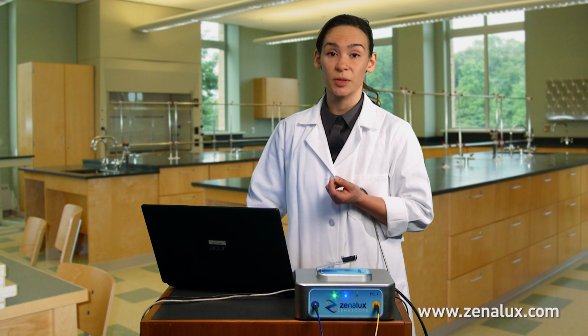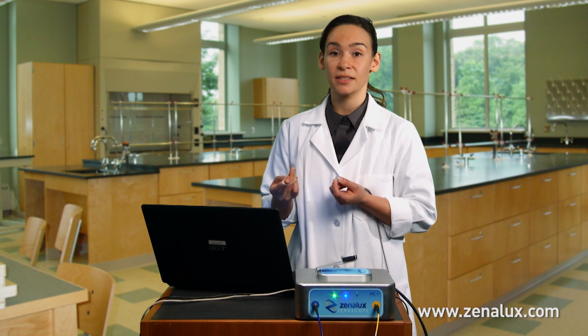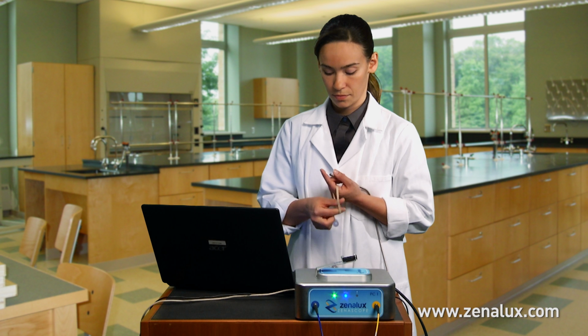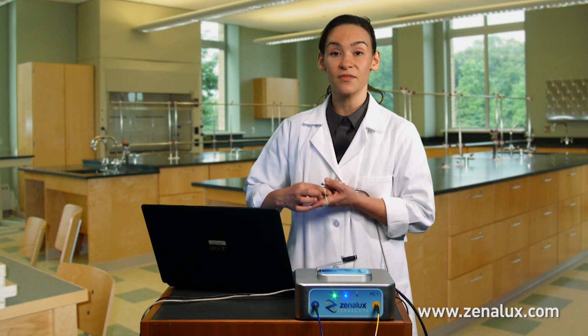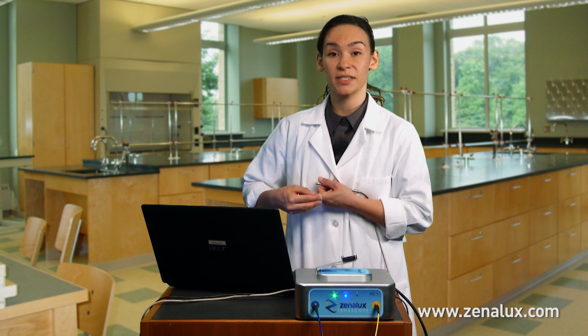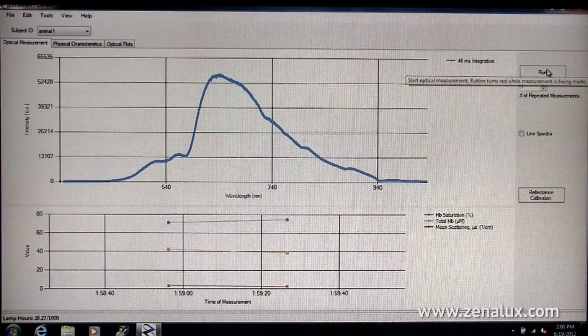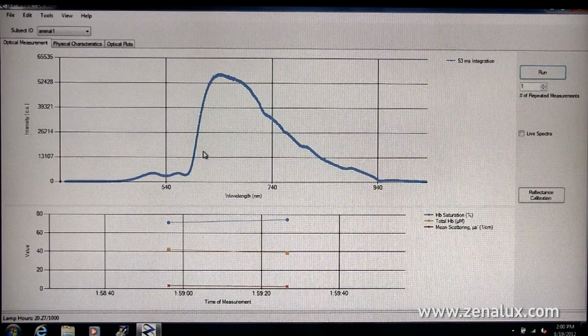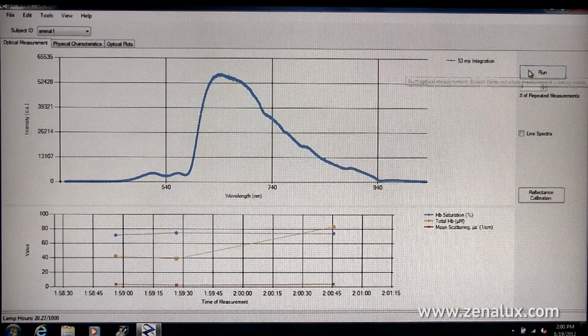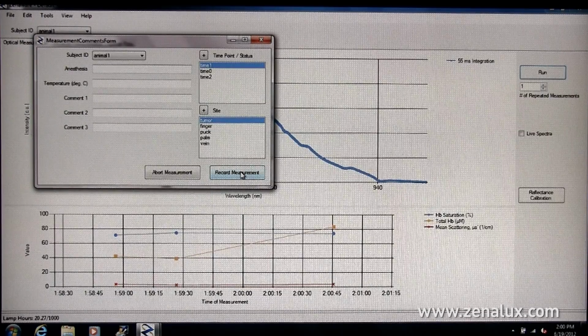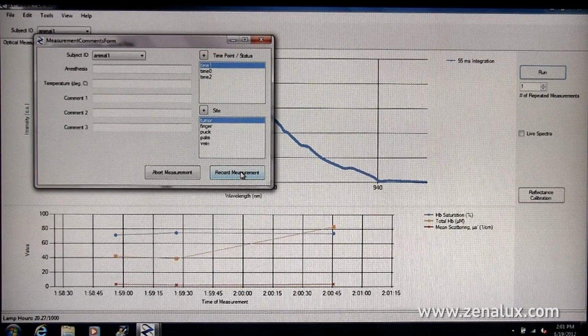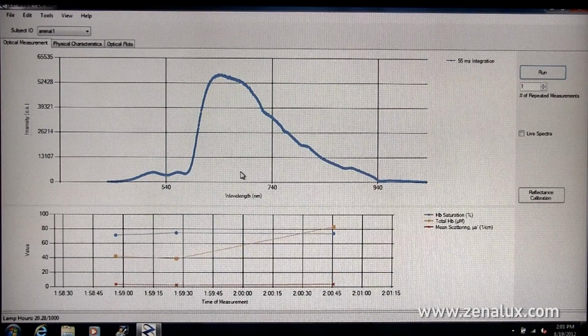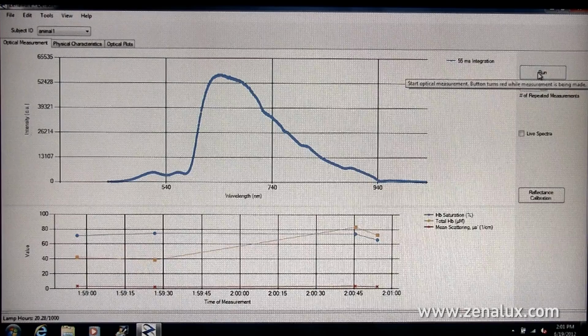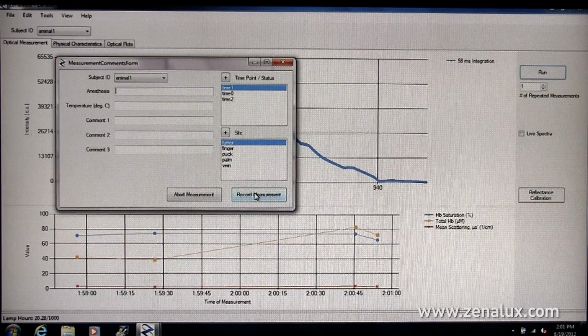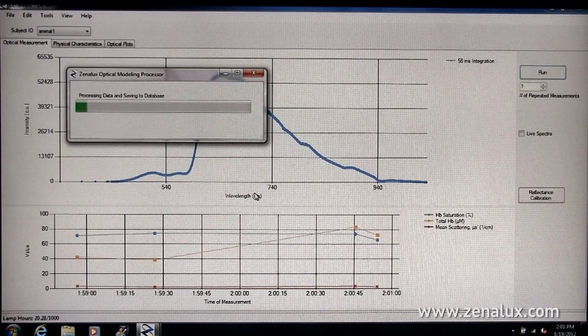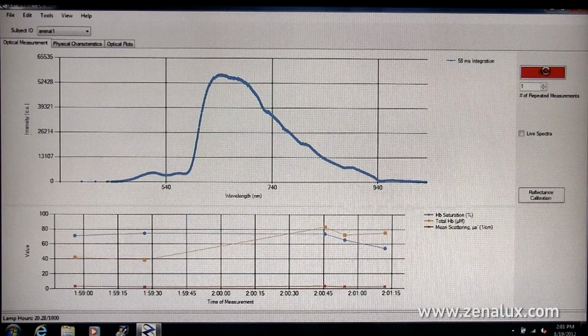What I'd like to do now is apply the perturbation to the sample. I'll do that by using a rubber band to constrict the blood flow in and out of my fingertip. Then we'll take a series of measurements over time and see how hemoglobin saturation changes. To take additional measurements, simply hit Run and record measurement for each measurement. Wait until your second series of analyses appears before hitting Run again. And record measurement. Run. Record measurement.